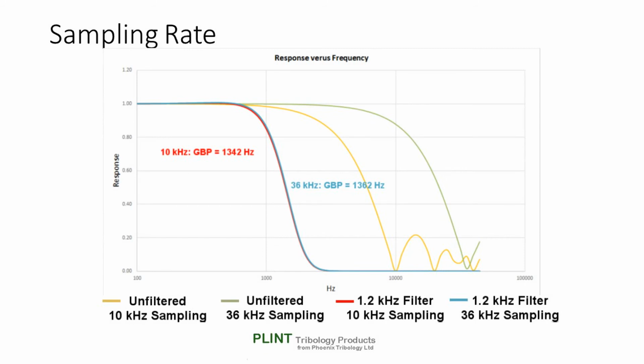The measured amplitudes of signals sampled at half the Nyquist sampling rate are attenuated to 64% of their true value. It is good practice to sample at higher rates than the Nyquist rate within reason. The graph shows the difference between the combined effects of a 1.2 kHz input filter and the attenuation effects of 10 kHz sampling and 36 kHz sampling. The differences are barely noticeable.